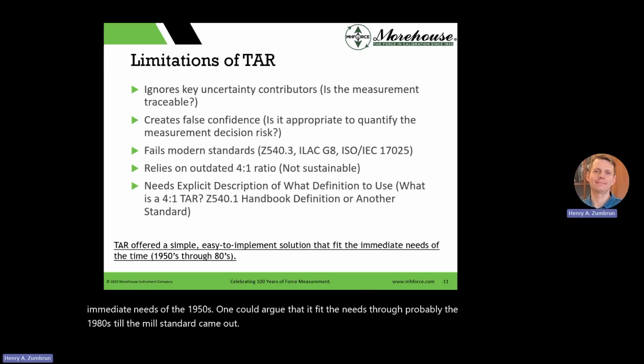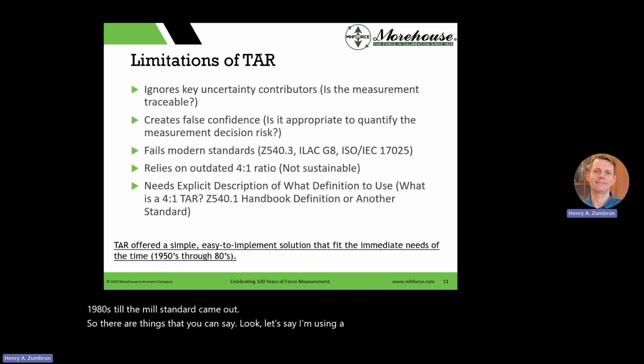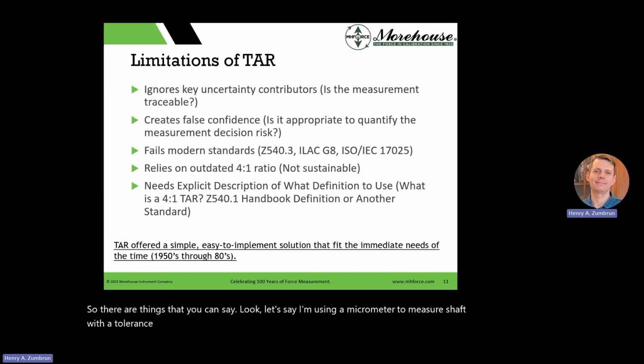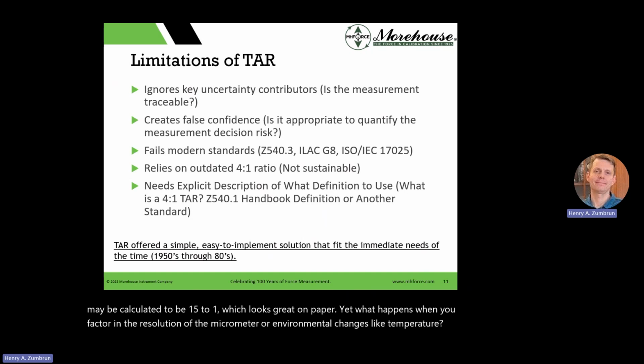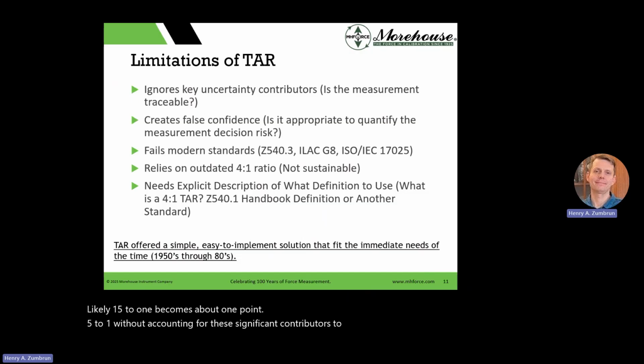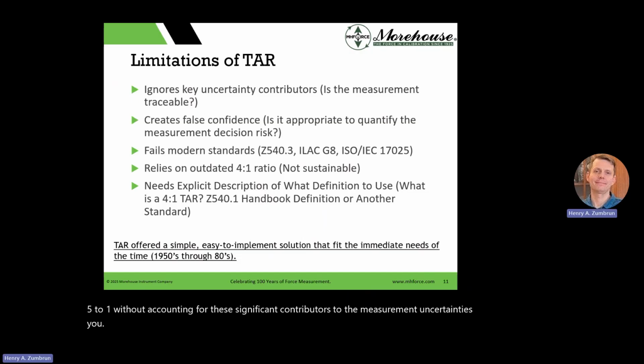So there are things that you can say, look, let's say I'm using a micrometer to measure a shaft with a tolerance of 0.015 millimeters. If the calibration has a tolerance of 0.001 millimeters, the TAR may be calculated to be 15:1, which looks great on paper. Yet, what happens when you factor in the resolution of the micrometer or environmental changes like temperature? Likely 15:1 becomes about 1.5:1 without accounting for these significant contributors to the measurement uncertainties. You risk making a bad measurement. It just provides that false sense of security.